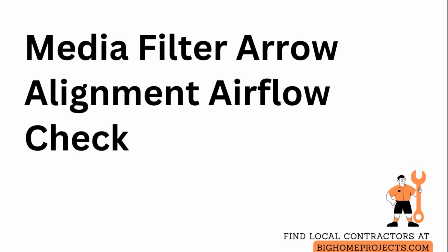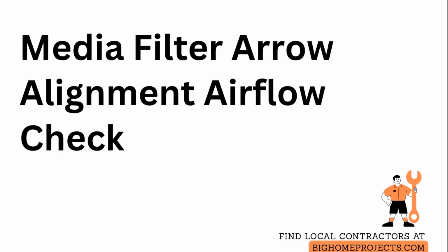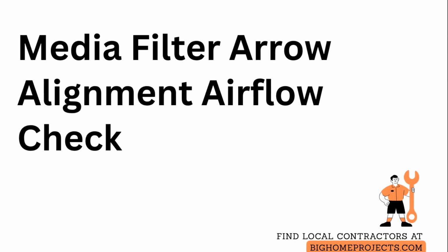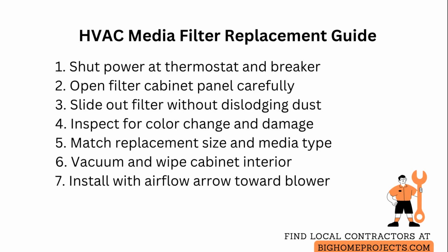Replace and inspect a media filter in your HVAC system, starting with safety and a clear plan so airflow and performance are restored quickly. First, shut power to the unit at the thermostat and at the breaker so the blower cannot start while you work.